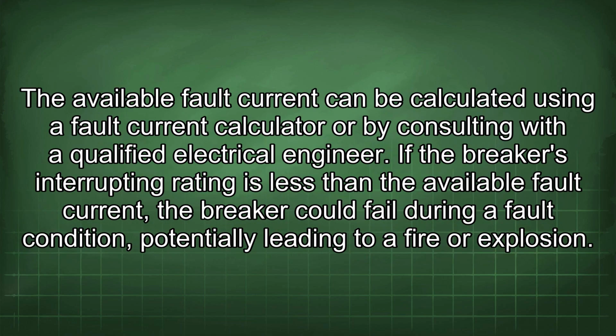The available fault current can be calculated using a fault current calculator or by consulting with a qualified electrical engineer. If the breaker's interrupting rating is less than the available fault current, the breaker could fail during a fault condition, potentially leading to a fire or explosion.